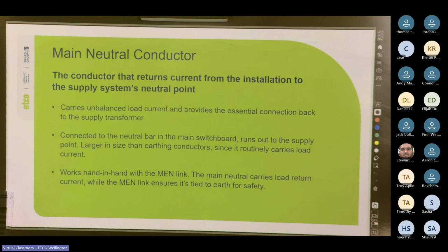Cool. Our main neutral is the main return highway for the installation. It's always carrying load current, and the MEN link ensures the neutral is never floating. It's locked to earth potential for stability and safety.